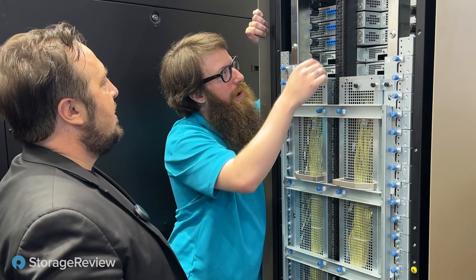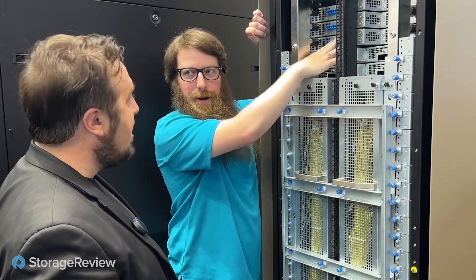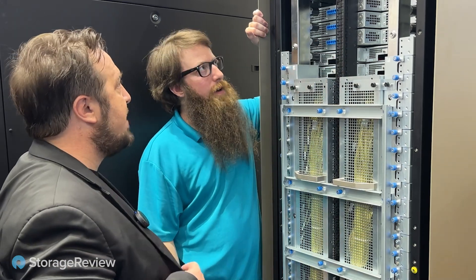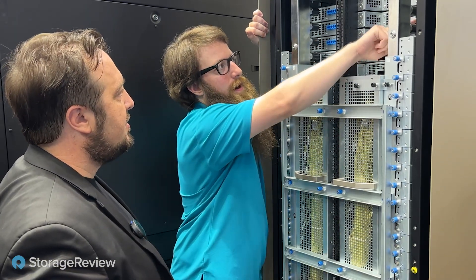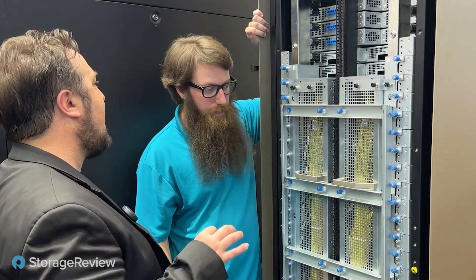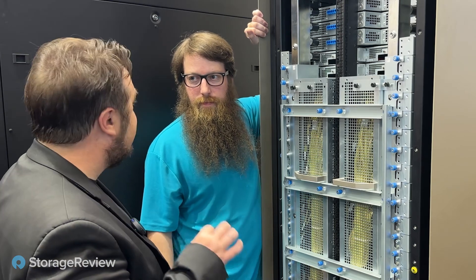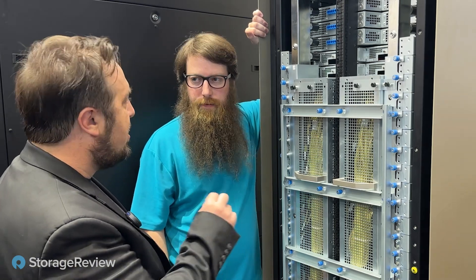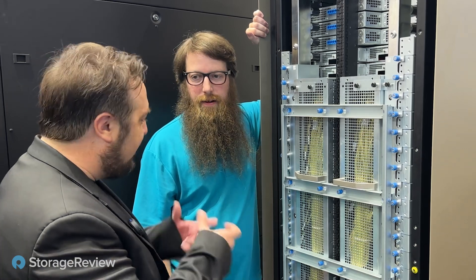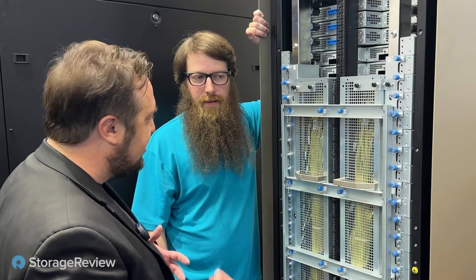We've got our big OCP bus bar here, you can see our power supplies and where all the whips go in. There's a management network up on top. And then we have our Zero Drip connectors. When we're talking Zero Drip, the amount of condensation you get is really just 0.0025 cc's of liquid — the equivalent of breathing on your glasses. There's no drop.